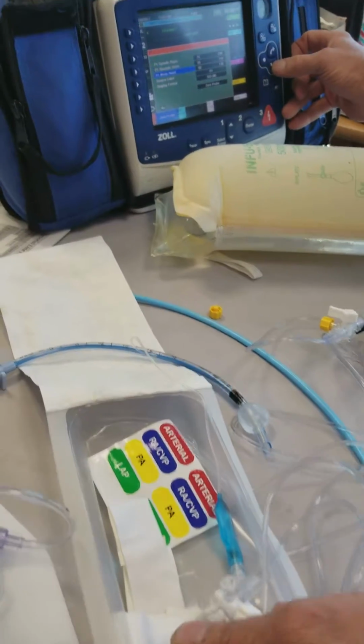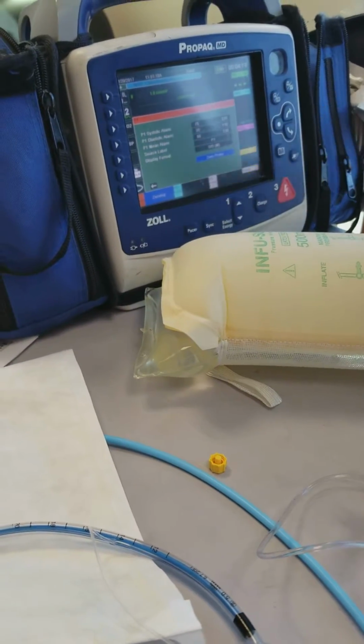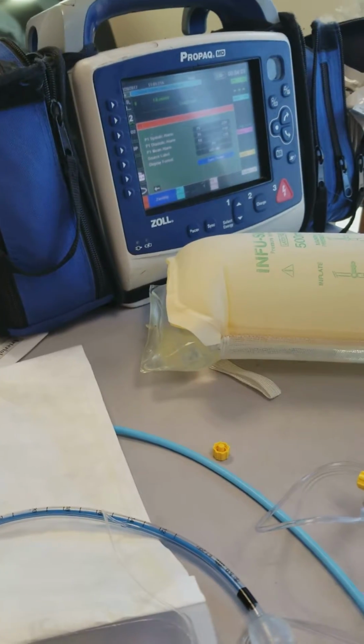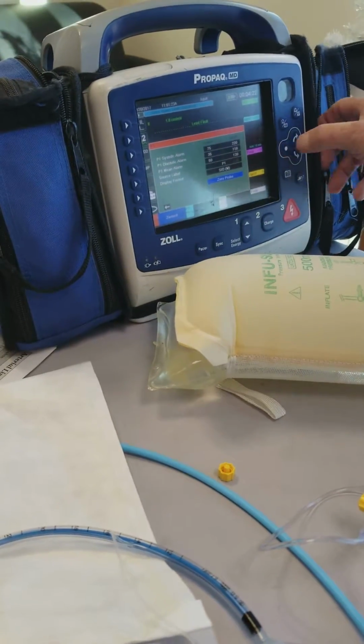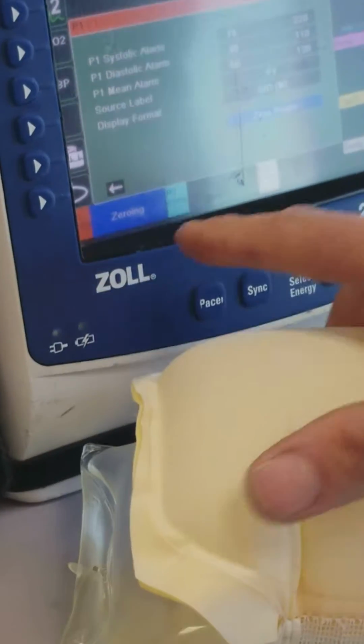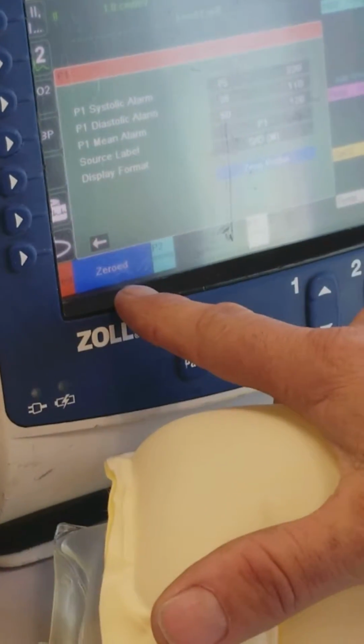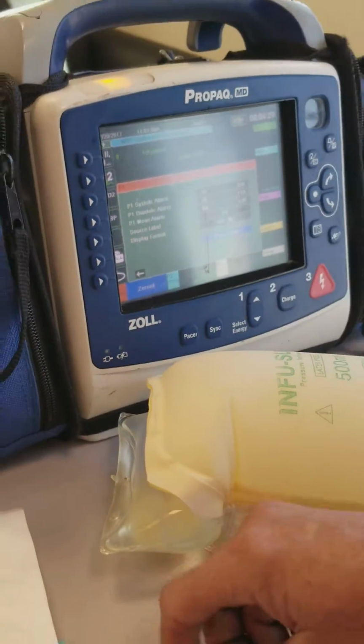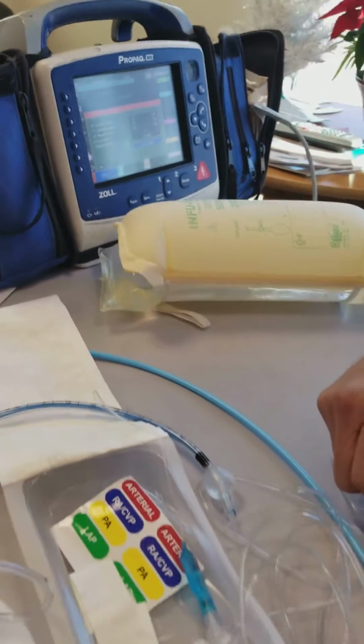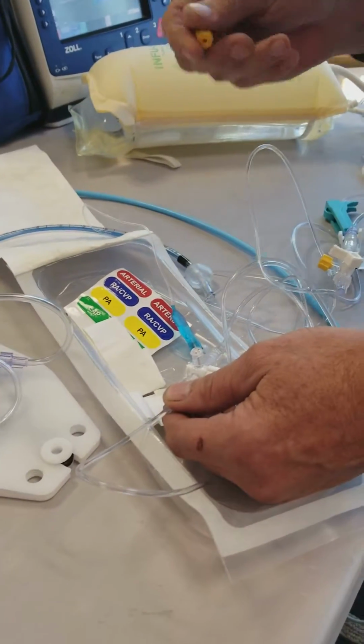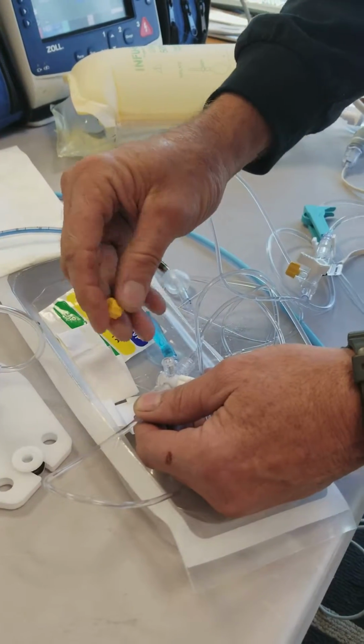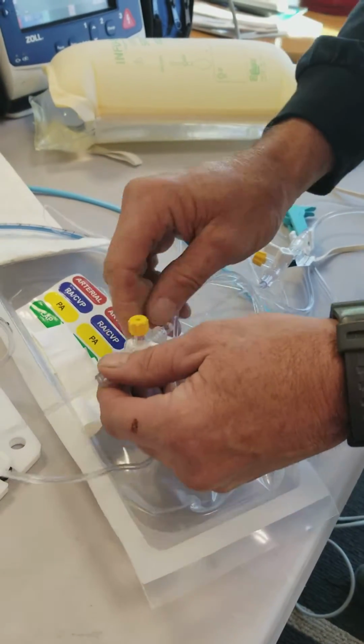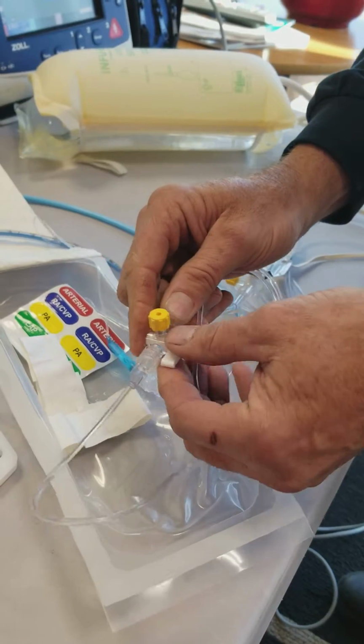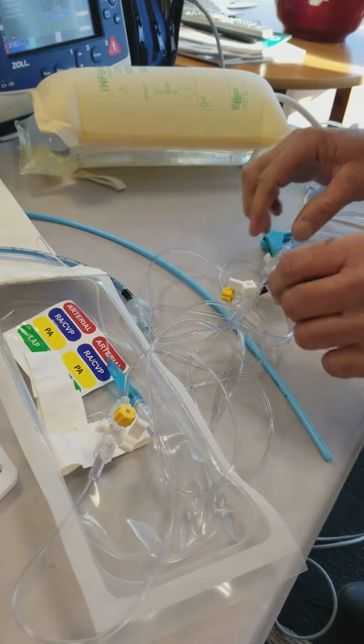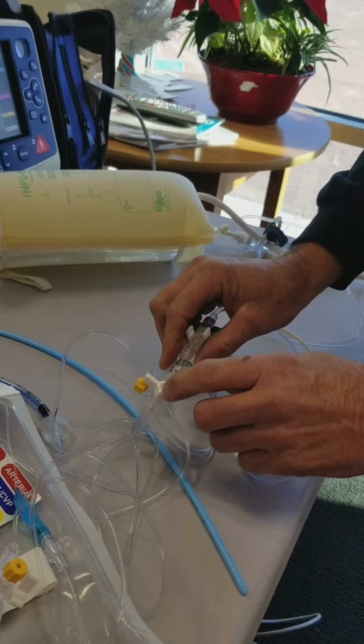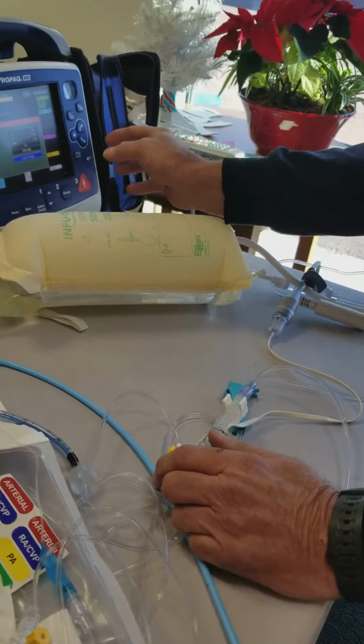Okay, I have the zero probe. And it is zeroing. And it says 0. Now I bleed a little bit of water or fluids out of it. It's normal saline. I replace the cap. I turn it back off to my cap, back onto my transducer, and I can go to my monitor.